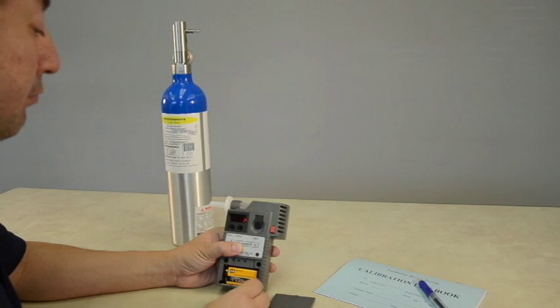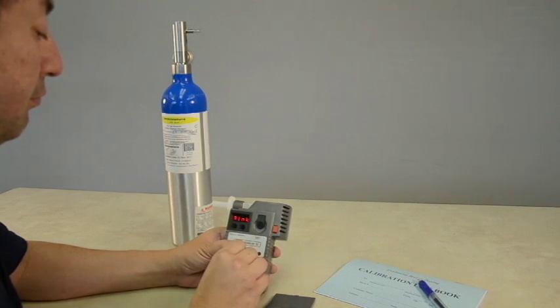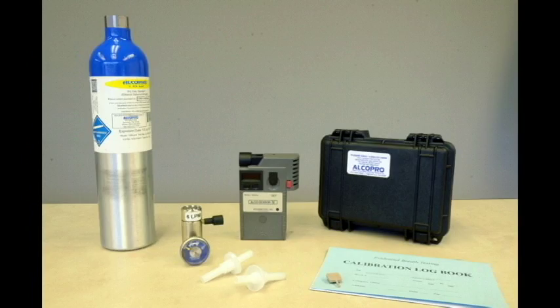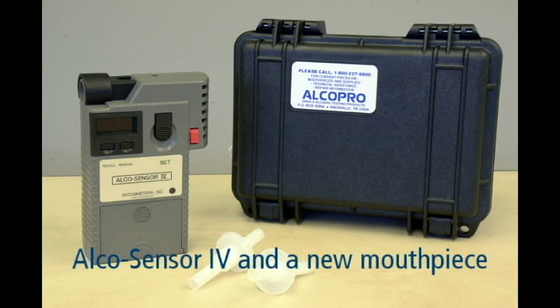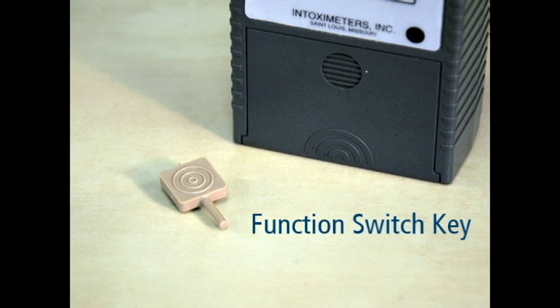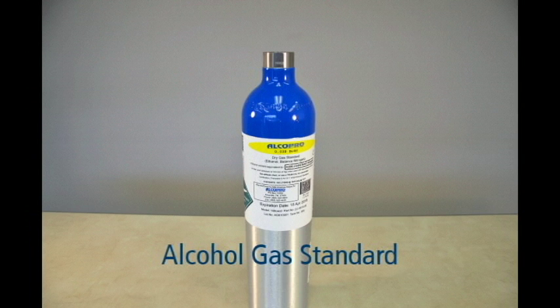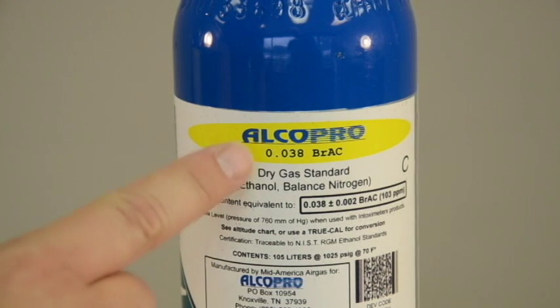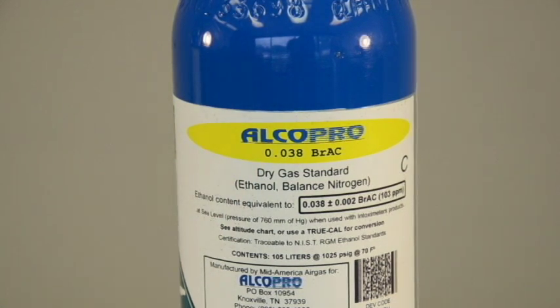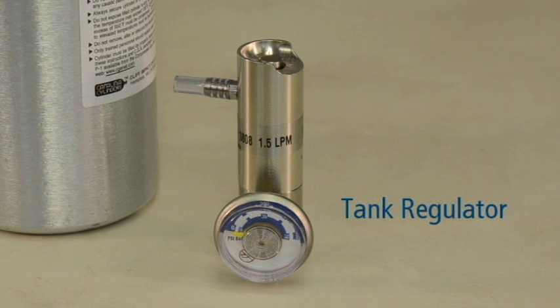This video shows the steps for performing a calibration adjustment on the AlcoSensor IV with memory using a dry gas standard. To perform a calibration adjustment, you will need the following materials: your AlcoSensor IV with memory device and a new mouthpiece, the function switch key that came with your device. You will need an alcohol gas standard. We will be using a dry gas standard with an ethanol content of 0.038 BRAC at sea level. The dry gas standard concentration can be located on the gas tank label. You will also need a tank regulator to attach to your dry gas tank.